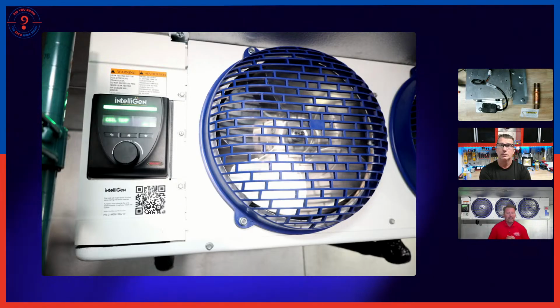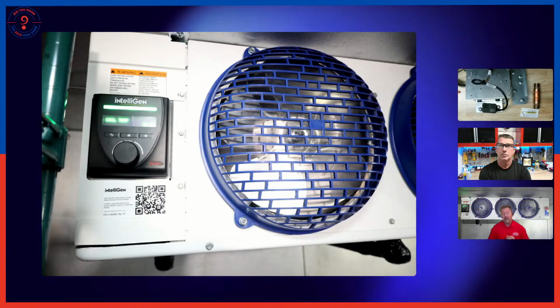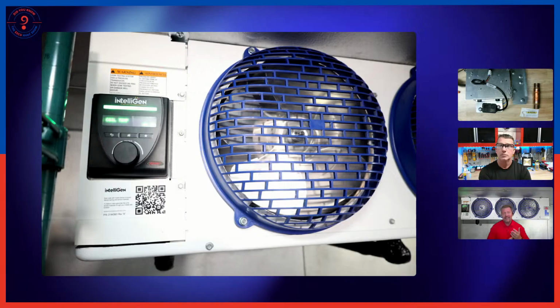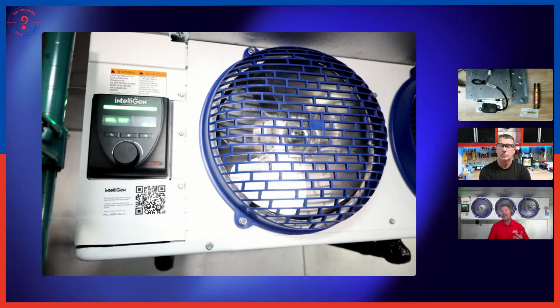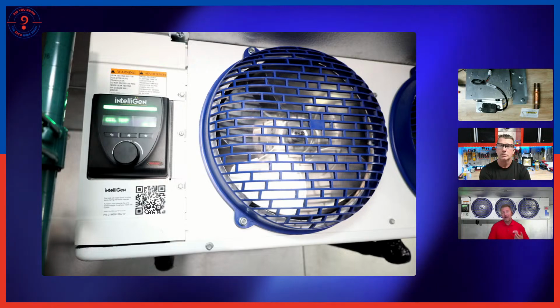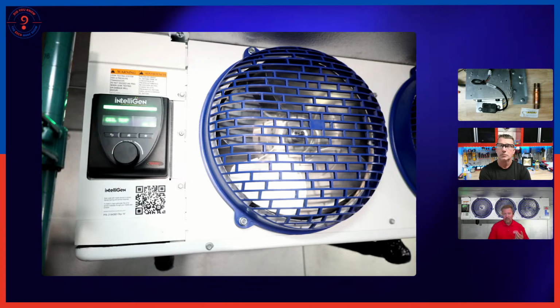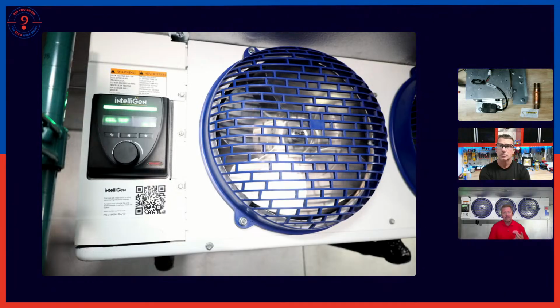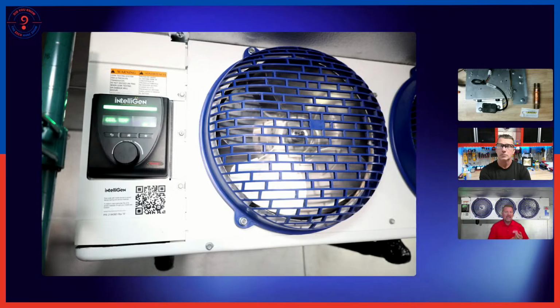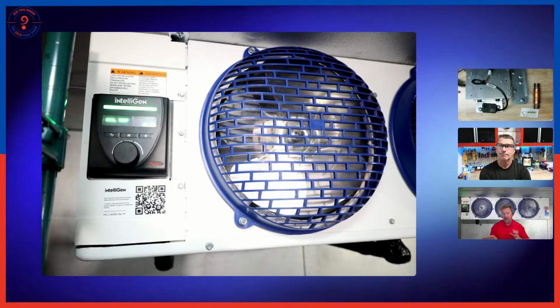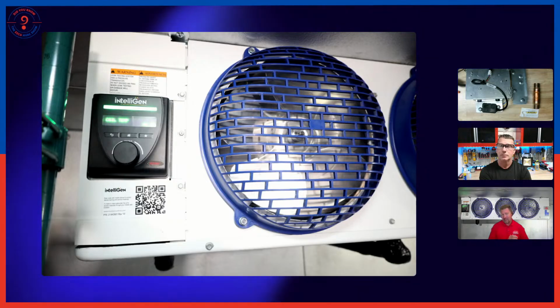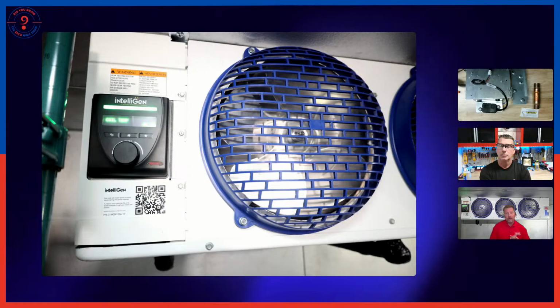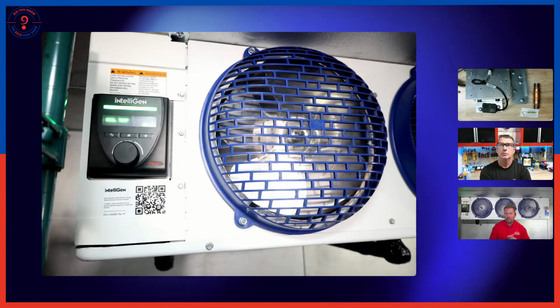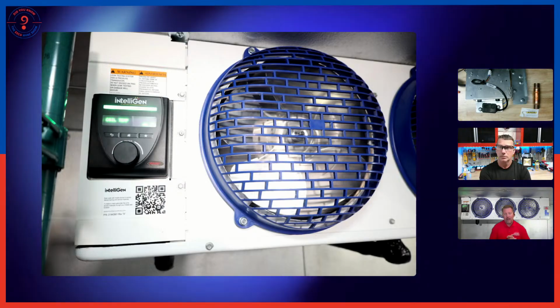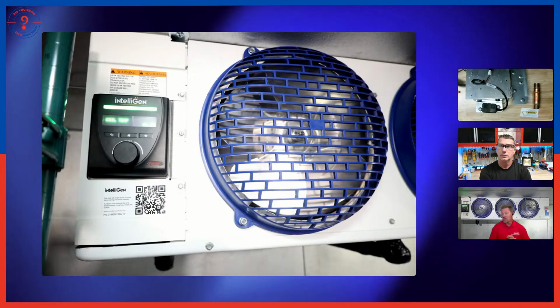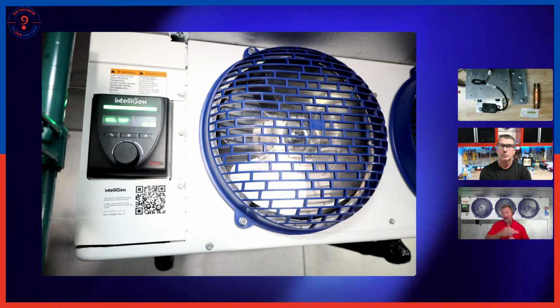Intelligen is very simple. It does eliminate the need for a defrost timer, fan delays, liquid line solenoid, and it eliminates the necessity for wiring between a condensing unit and your evaporator. This Intelligen evaporator can be powered off of its own power supply, and there is no communication necessary between the evaporator and the condenser unless you have an Intelligen condenser, which would require you to have low voltage wiring between them. You would run basically a traditional thermostat wire with a minimum of 2 wires, and our control circuitry is going to be powered by our Intelligen evaporator.